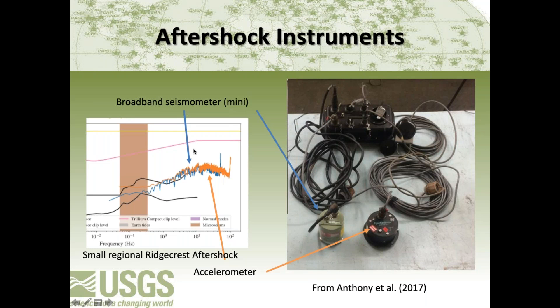Going back to our two spectra from the aftershock, since we have an earthquake in there, the data doesn't lie between the two Peterson lines — which is good because it means we have signal. The orange curve is from the EpiSensor strong motion sensor with a higher clip level, and the blue curve is from the Trillium Compact with a lower clip level but also a lower noise level. This is what we might expect from a small regional event recorded on two different co-located sensors.